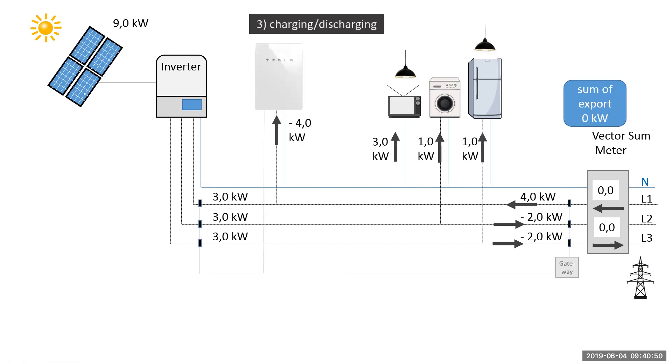Add the battery, we want to take that surplus into the battery four. But because it's a three-phase system, we've got one battery connected here. This would be four kilowatts being pulled in on L1, two kilowatts going out on L2, and two kilowatts going out on L3. Still equaling net sum export of zero.